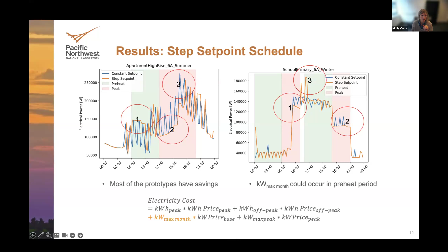So first looking at the step set point schedule or set point approach, we did find that this did have some energy cost benefit, but one thing that we found at times, which you can see on the right-hand graph that's circled as area 3, is that we ended up with these big spikes of demand during the preheat window when we had set the aquastat set point up to 180, that the tank was firing at full bore during that time and could cause a building peak demand, which was impacting the bill for that month. So that was an issue with this control strategy.